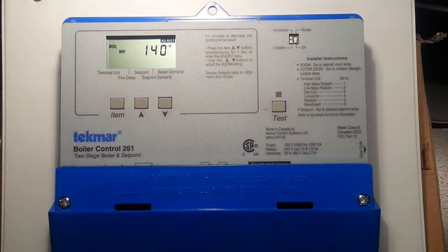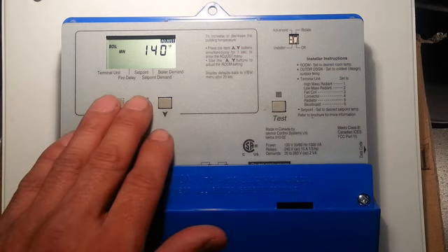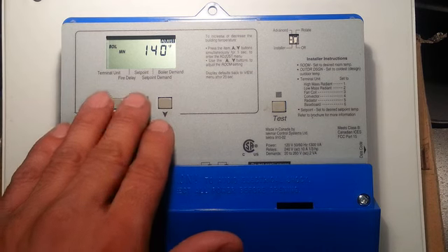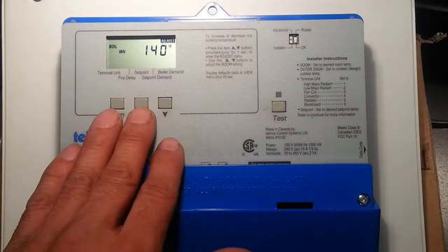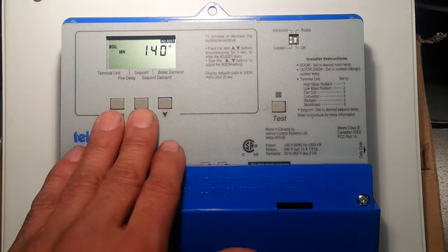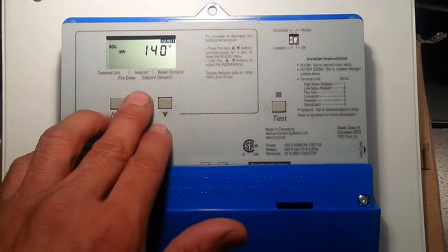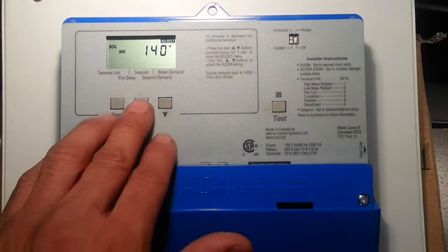The next setting is the boiler minimum temperature. This is something that you have to be very careful with if you're running a steel boiler or a copper fin boiler. Steel boilers typically can't handle anything below 140. Copper tube boilers, anything below 130 creates a condensation problem, and condensation on a steel boiler causes rust, and the boiler will rust out and plug up fairly quickly.